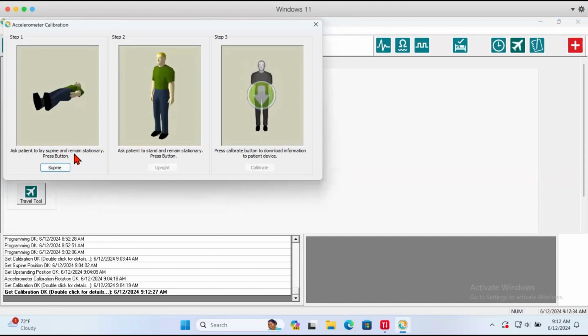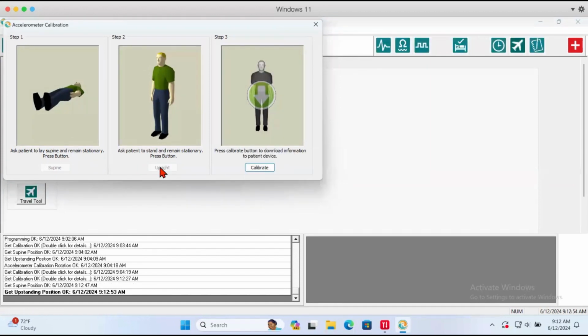Ensure the wand is positioned over the patient's device for this process. The accelerometer calibration window will appear, requiring configuration for two postures to calibrate the position sensor. Instruct the patient to lie down flat in a supine position and select the supine button to save this position. Afterward, ask the patient to stand upright and click the upright button to save the upright position.